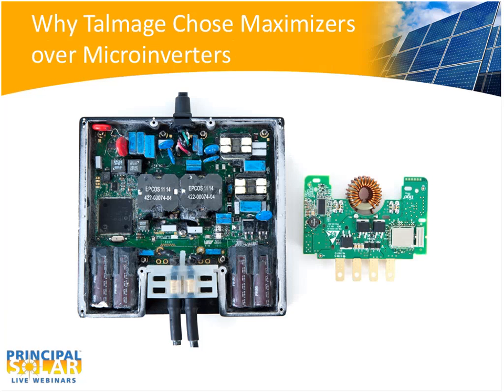Now, the reason our system is special, and the reason I'd think the Talmage folks chose us instead of a microinverter - in addition to the fact that microinverters aren't nearly as commercial scale as a maximizer - is that if you're doing the math in terms of cost, efficiency, and reliability, which are the most important things, there are secondary things like being able to install one module at a time. But when you've got 9,000 at once, you don't really care whether you can have a 3-module array. If you want a 3-module array, microinverters are great. But if you've got anything larger than a full string, a system with a maximizer and a best-in-class central inverter gives you a much better cost structure, efficiency structure, and reliability profile.